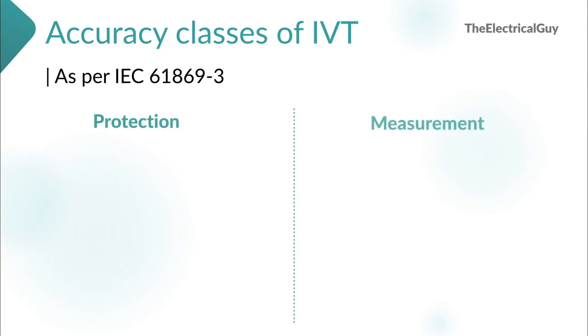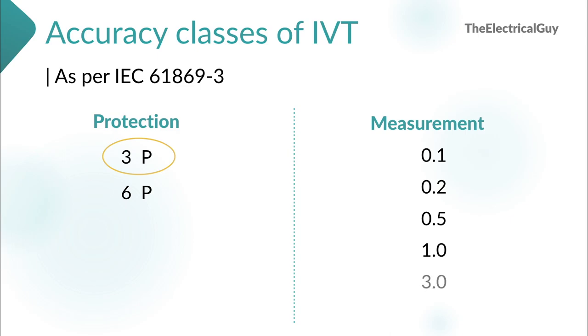IVT has two types of accuracy class: protection and metering. In protection, as per IEC 61869-3, there are two types: 3P and 6P. The number 3 or 6 indicates the percentage of voltage error allowed, and the letter P indicates protection. 3P is more accurate than 6P as the voltage error allowed is less, making it the most commonly used protection class in IVTs. In metering, we have classes 0.1, 0.2, 0.5, 1.0, and 3.0. Again, the number indicates the percentage of voltage error allowed. So if a secondary winding has class 0.2, only 0.2% error is allowed. The 0.2 class is the most commonly used class for measurement in voltage transformers.